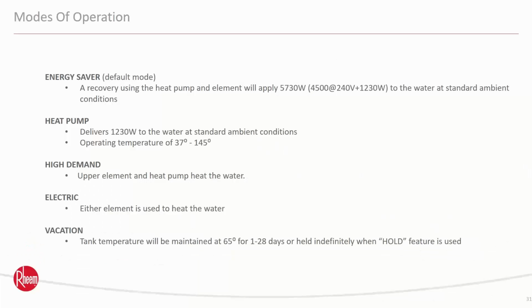As far as the modes of operation, like I said, there's 5 modes of operation. You've got energy saver, heat pump, high demand, electric, and vacation. This thing comes delivered usually in Energy Saver, which is using the heat pump and the elements to heat the water, only using the elements when it needs. If you put this in heat pump mode, then it's only using the heat pump to work. This is going to be the most efficient way to do it. But understand that in heat pump mode, when this thing's depleted, it's going to take roughly 8 hours to recover and get back up to temperature with the heat pump only, okay?